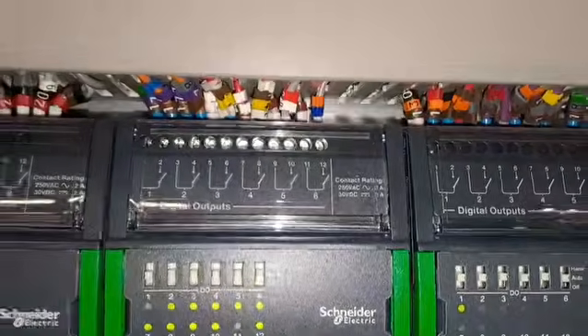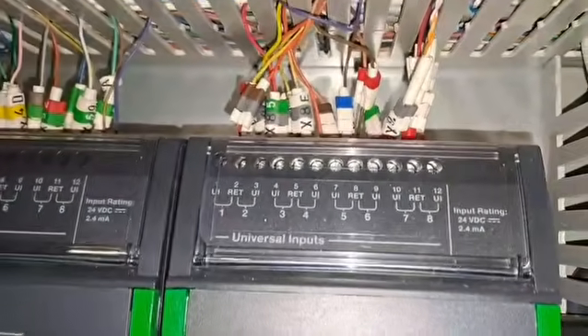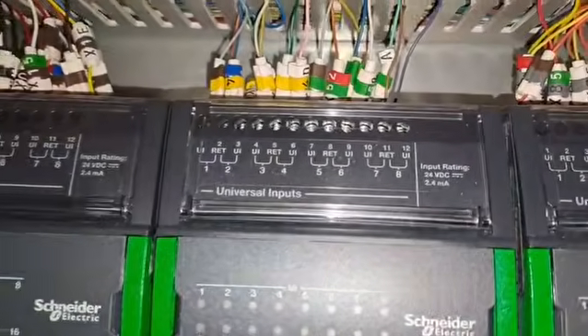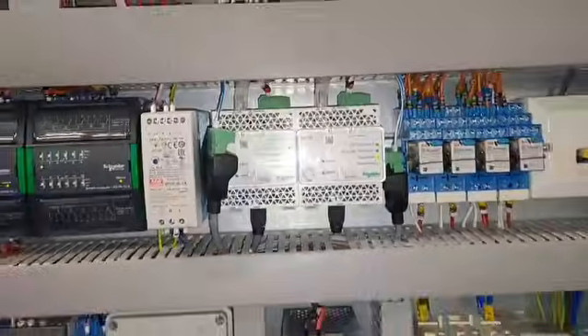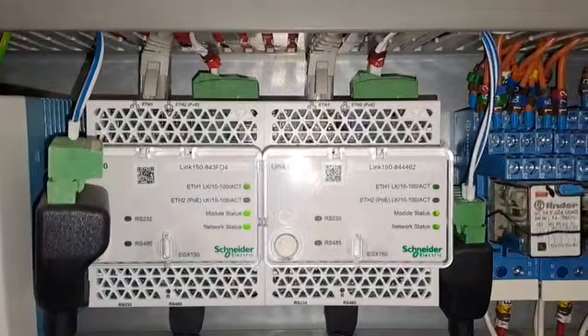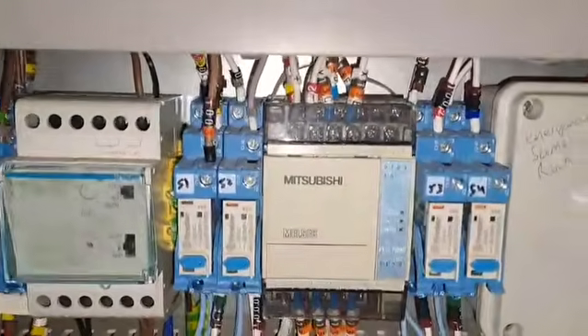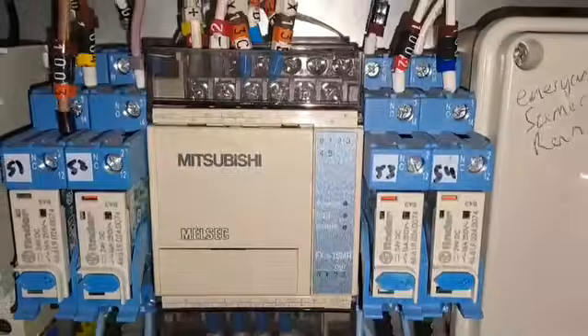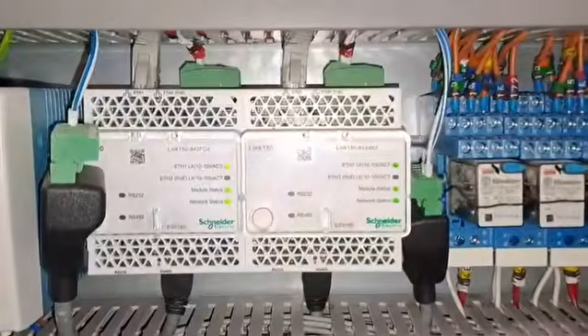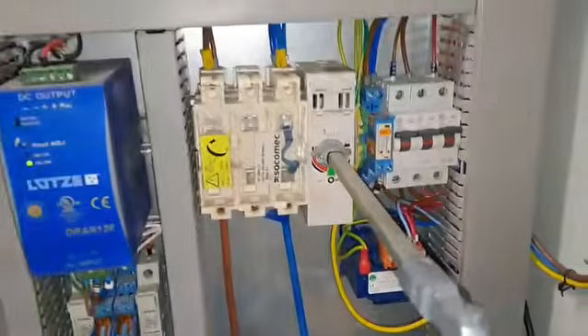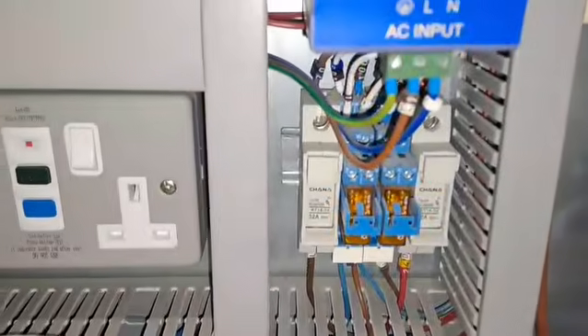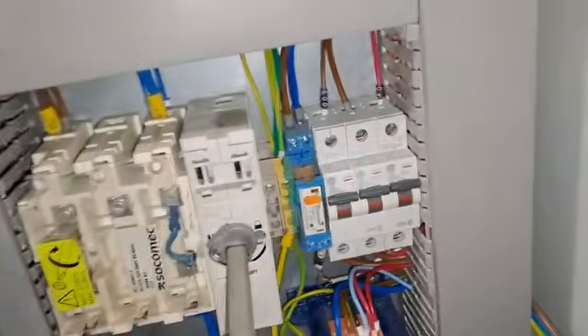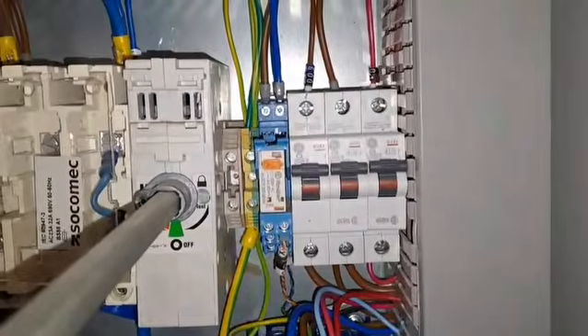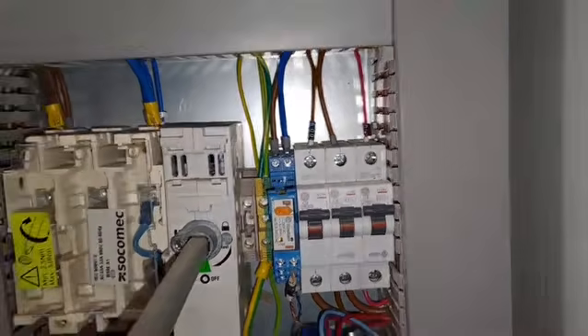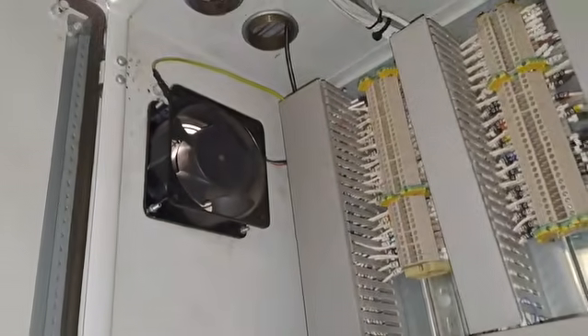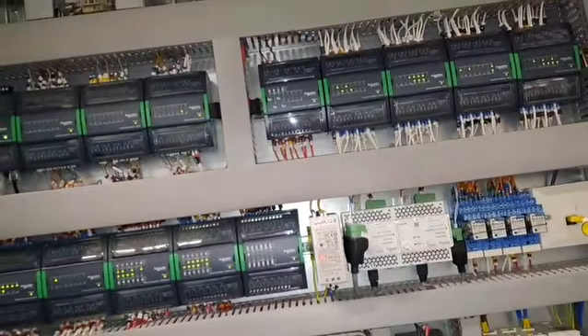And then up here, digital outputs, and then up here you've got universal inputs. This looks like for Modbus communication, and this looks like it's communicating with the field devices, and so is this as well. Local isolator, relays all over the place. These are breakers, so you can see what they're rated to. This one C2, C6 and C4. And that fan up there is not running, so it's not going to keep the panel as cool as it should be.